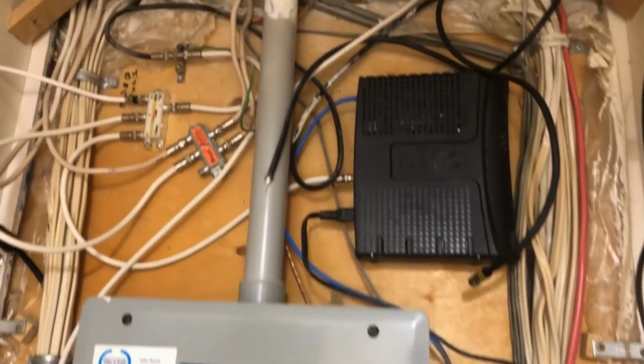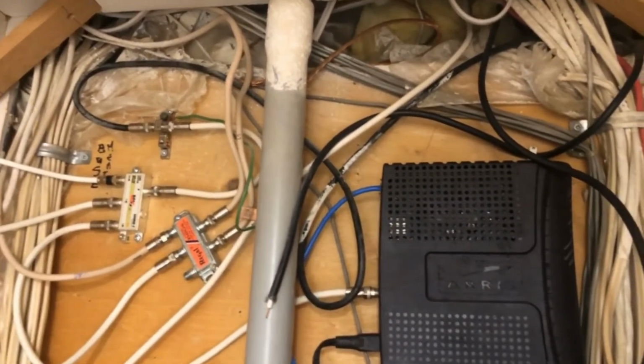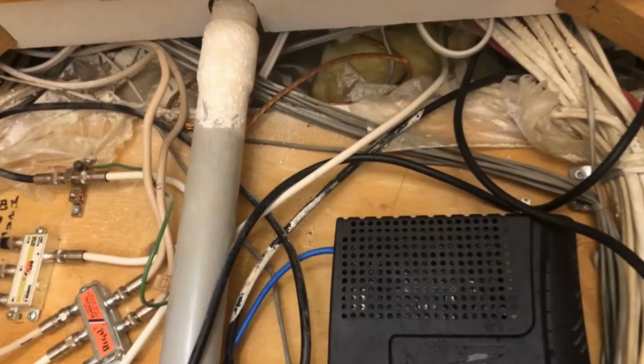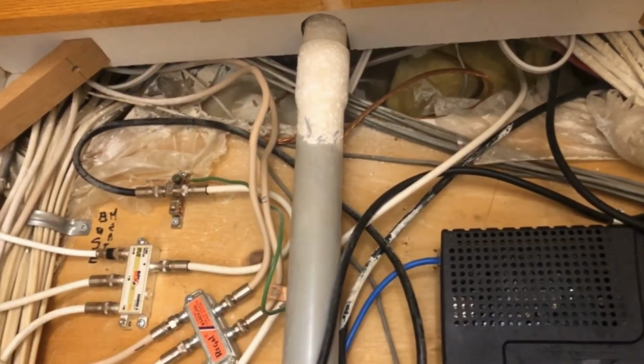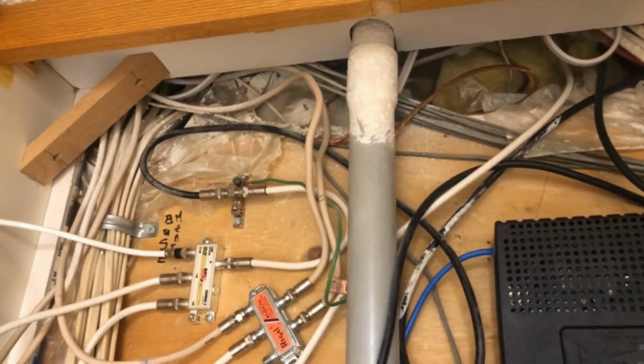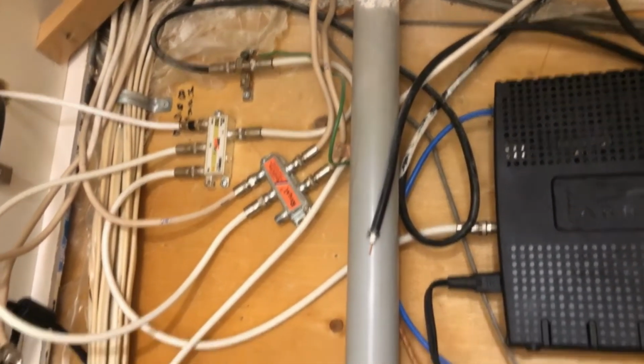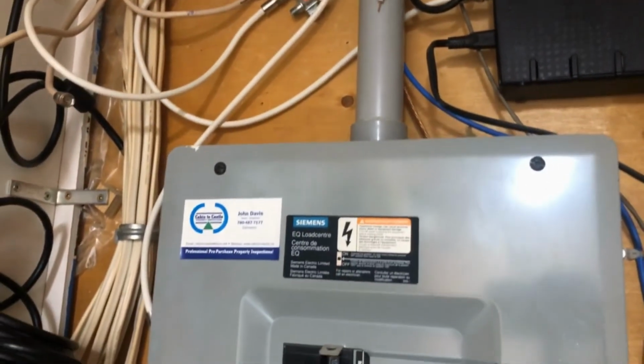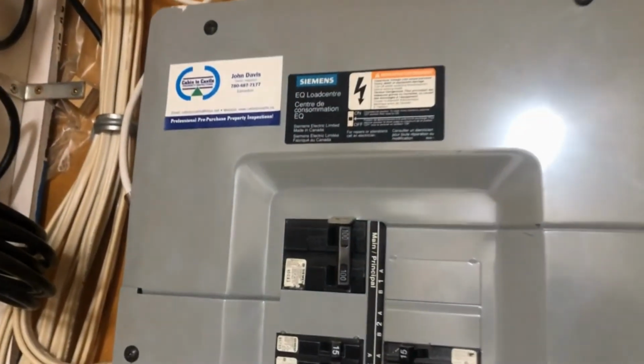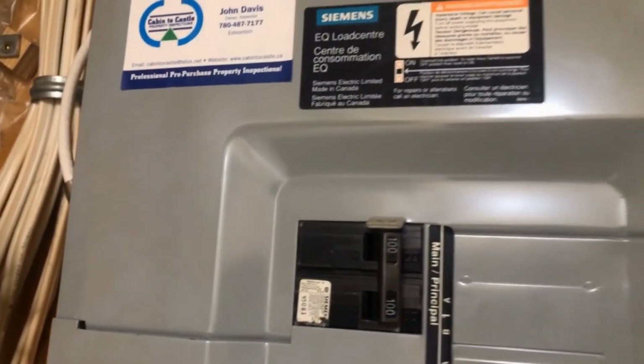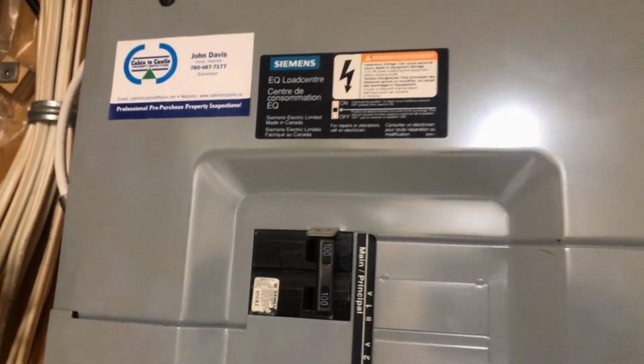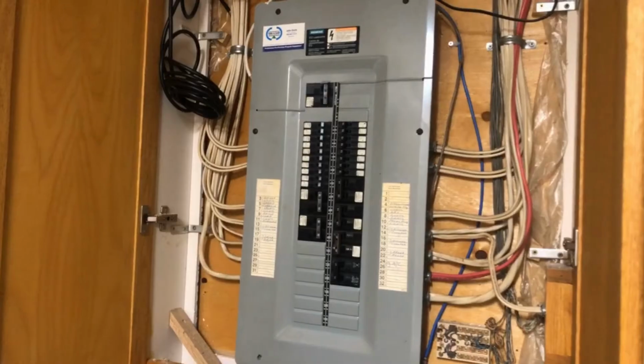So when we were outside, we noticed that the electrical service meter had a conduit coming into the house, and this is actually where the conduit comes through, up through there. These are your main service conductors coming into your home, and they go into your electrical panel in the top section here - we call it the service section. You can see I have a 100 amp service, with a 2-pole 100 amp breaker, typical for so many homes.